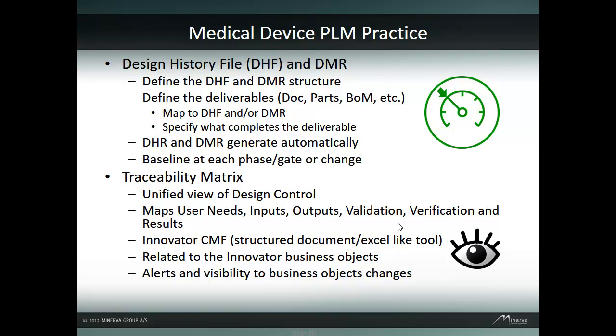The traceability matrix is a unified view of the design control. It utilizes the content modeling framework in an Excel-like format to map user needs, design inputs, and outputs to their verification and validation results. The key differentiator from an Excel spreadsheet is that the traceability matrix is a structured document with relationships to the Innovator business objects. As these business objects change, the traceability matrix can receive alerts and updates. For example, when a requirement for a design input changes, the change will be highlighted in the traceability matrix, notifying the user to review the validation plans, verification plans, and the design outputs.